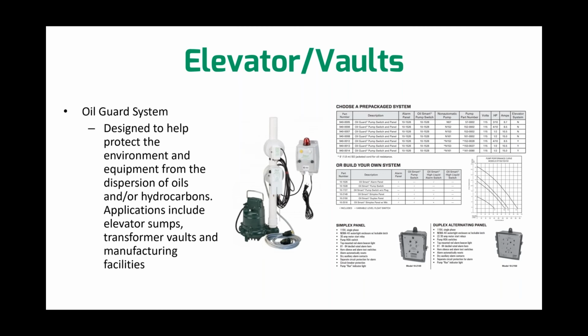Our pump systems within the oil guard system, if it senses oil, it does not shut the pump off, because you still want the pump to be able to pump the water that's below the level of the oil. Now, there are some units out there, not ours, that if it does detect oil at all, then it shuts the system completely down, which is not what you want. You want this thing to be able to continue pumping the water in the system, even if there is presence of oil. But again, when that alarm sensor detects that oil, it sends that notification to that alarm panel, and wherever that's mounted, the electrician can use the dry auxiliary contacts that are within the alarm panel, and you can run wire from this alarm panel to wherever else it needs to go to give notification to the maintenance person, whomever can see this and get these notifications that I need to get out there. There is oil in the system. It's not going to be pumped out. I need to get out there and somebody needs to take care of it.